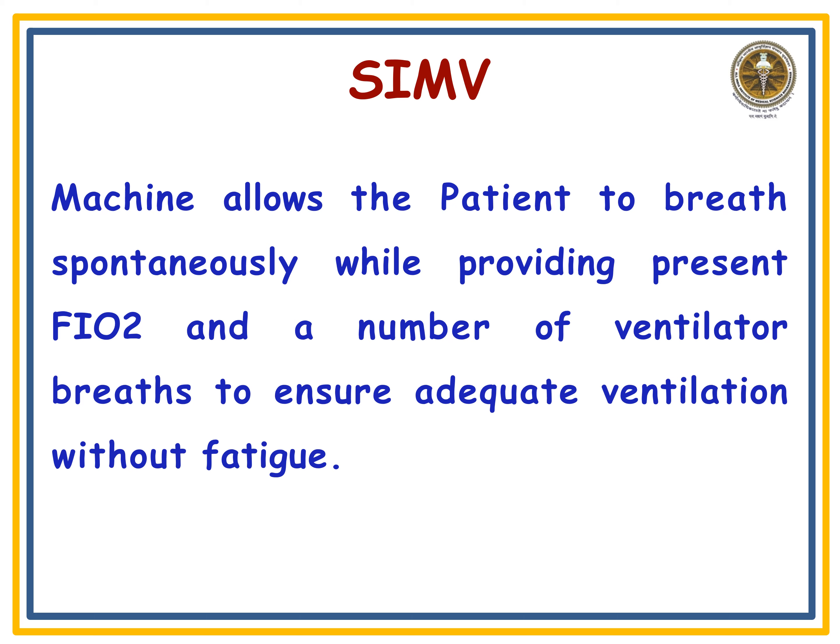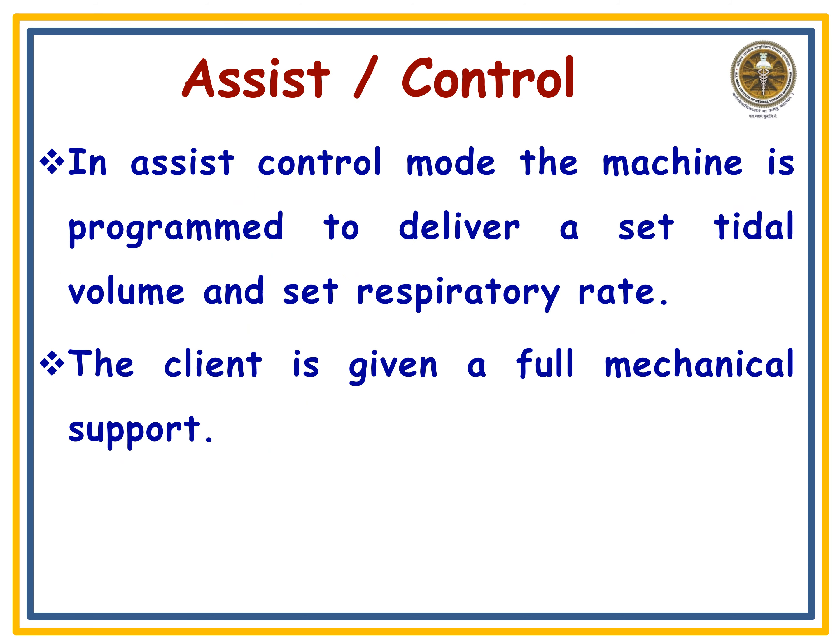The next mode is SIMV — synchronized intermittent mechanical ventilation. The machine allows the patient to breathe spontaneously while providing a preset FiO2 and a number of ventilator breaths to ensure adequate ventilation without fatigue. If the patient gets tired and cannot maintain the set parameters, the machine starts supporting the patient.